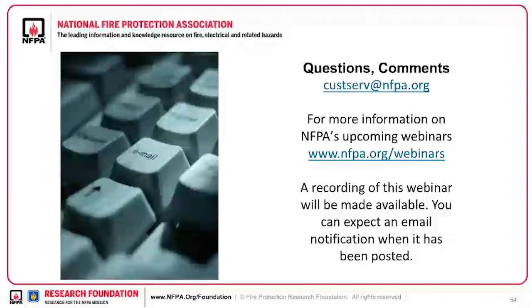Next question. Would creating a negative air pressure in a room once gases are detected deter a thermal runaway? My initial thought here is no. Thermal runaway itself is essentially when the battery starts to self-heat and the generation rate of heat is faster than the dissipation rate of heat. So the battery temperature just keeps increasing. And I've seen situations where the heat from one battery is sufficient to drive its neighbor into thermal runaway. And when that happens, it can just move all the way through the module. The batteries themselves are self-contained, and there's no need for fire. So the heating condition of the battery itself can drive the propagation of thermal runaway.